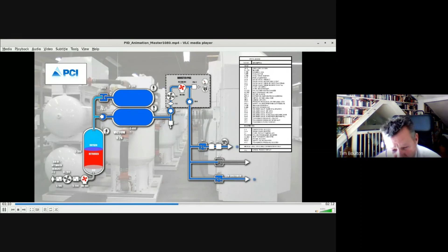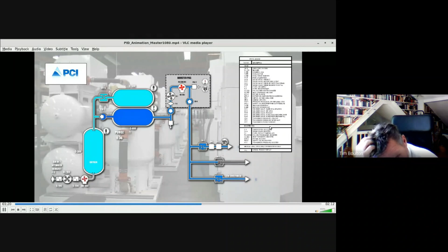Now it's in the vacuum phase, where oxygen is being drawn back through the system. You can see the pressure at minus 8. So now oxygen is going back through the sieve, expelling the nitrogen. In the last stage, the purge tank at the top of your screen pushes a little more oxygen through to make sure the sieve is completely clean.